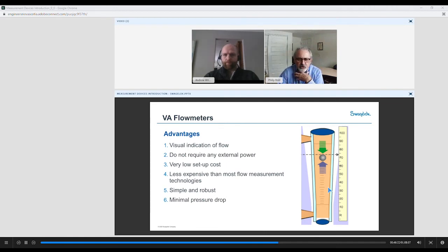So the advantages of using this type of flow measurement device: very simple. Visual indication of flow. You can see immediately, as you're standing there in front of it, where that ball is and where it correlates to a specific flow rate. Here you can see the taper of the tube, and as flow forces increase, it pushes that ball, which has a specific density, further up the tube. These have to be mounted vertically, and we'll talk about horizontal mounting in a few minutes. But as this pushes up the tube, the annular gap around the float becomes larger and allows for greater flow, and therefore correlates to a flow measurement indication.